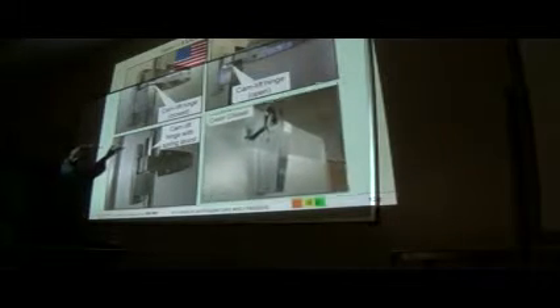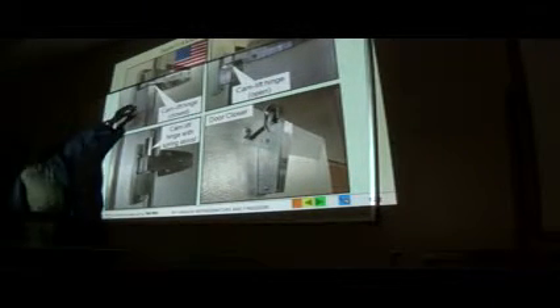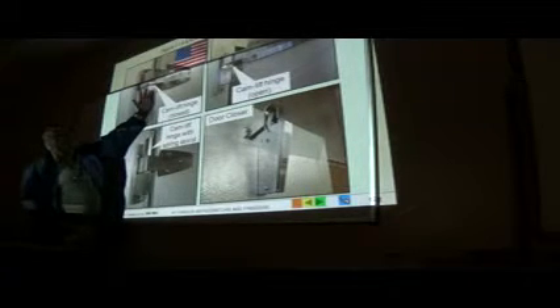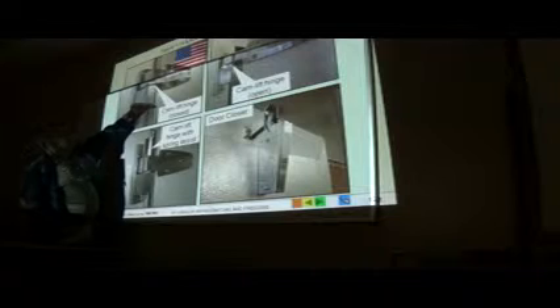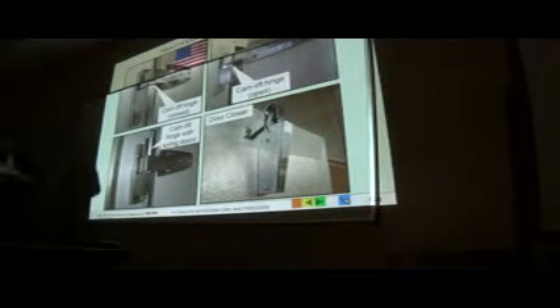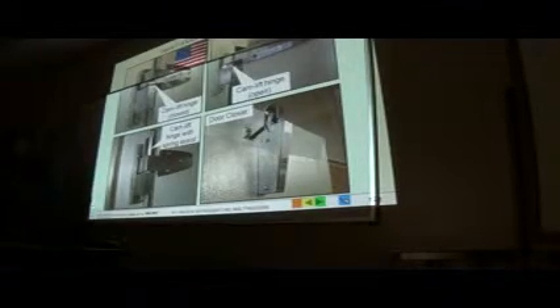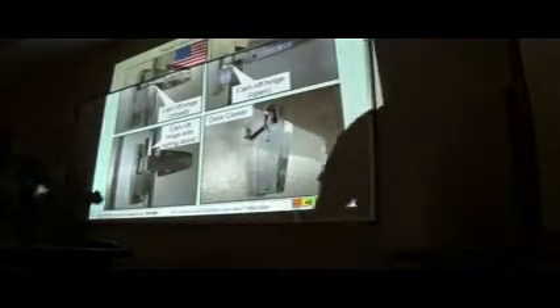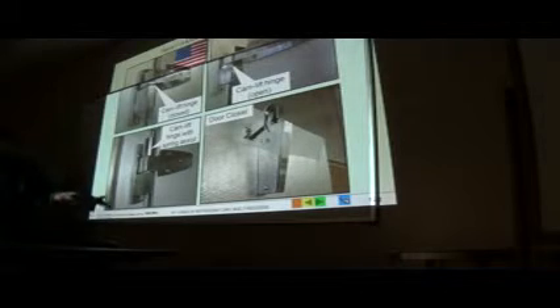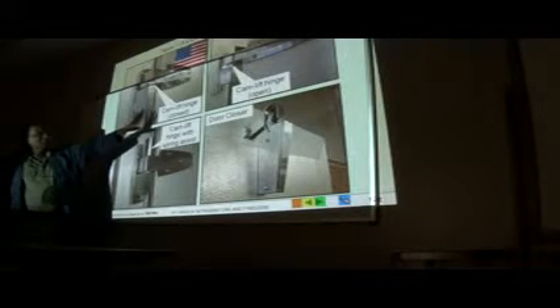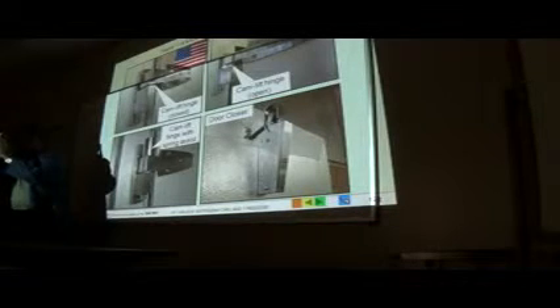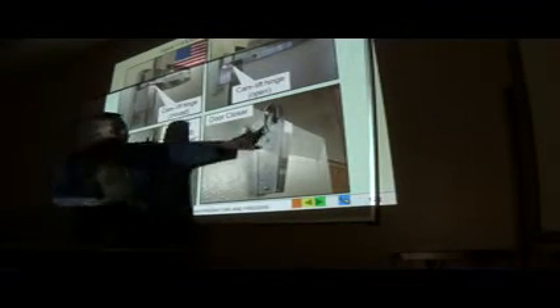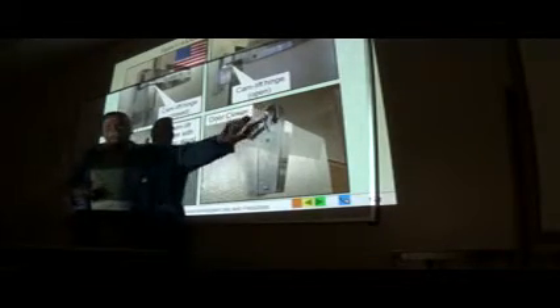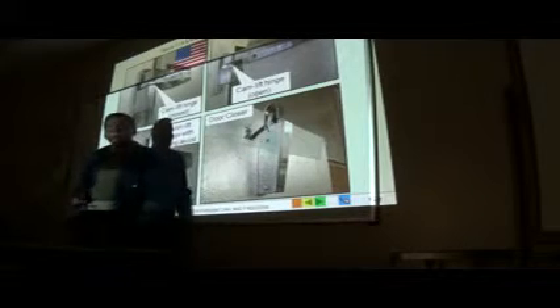What the hell? Okay, come up, take your time. See these hinges that say cam lift? As I open this door, there's a slope right under here and this door goes up. So as you release the door, it's self-closing, up to a point where you open it. If you open it wide back here, it's not going to close itself, but otherwise it closes itself. And as it goes in, for it to seal onto the gasket, because the gasket has a little spring, this pulls it that final inch or less and snaps it right into place.